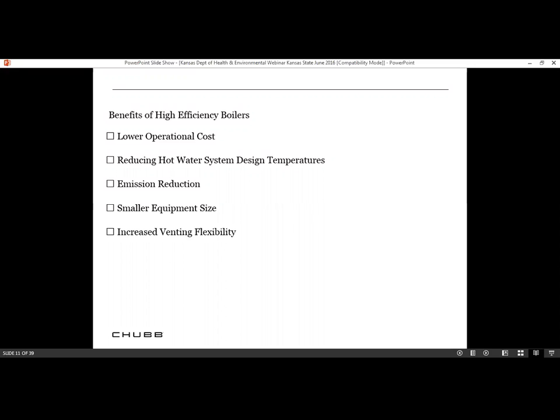One of the things that they do now with these new boiler installations is they bring the air from the outside. It's piped into the boiler, and then the discharge is piped outside through the roof or the venting apparatus. So you don't actually have to have the combustion air in the space itself, which adds to your efficiency.